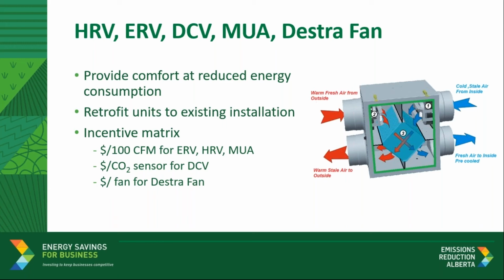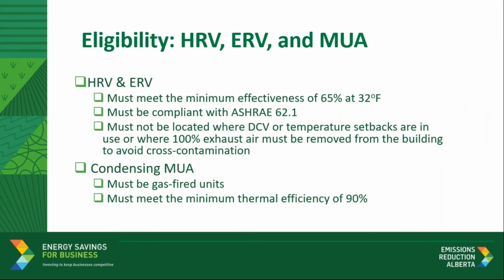Thanks, Surya. Can you tell us more about the eligibility? Absolutely. To be eligible for incentives, the HRV and the ERV must meet the minimum effectiveness of 65% at 32 degrees Fahrenheit. They must be compliant with ASHRAE 62.1, and they must not be located where you already have a DCV or temperature setbacks in use, or where 100% exhaust air must be removed from the building to avoid cross-contamination. There are certain buildings that have this requirement. If your application includes the condensing makeup air unit, then these must be gas-fired units, and they must meet the minimum thermal efficiency of 90% to qualify.